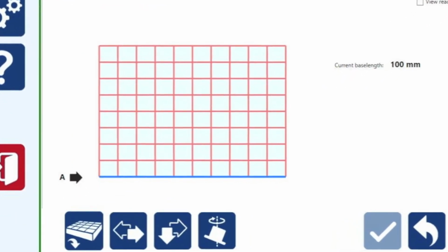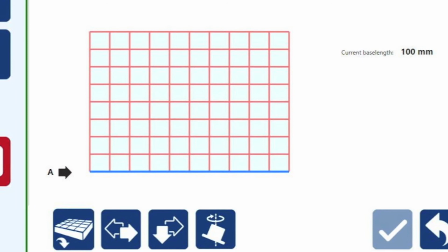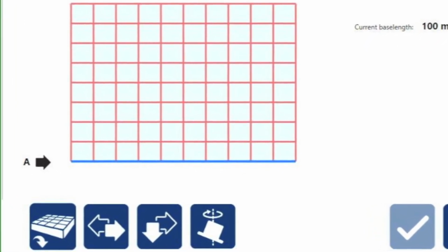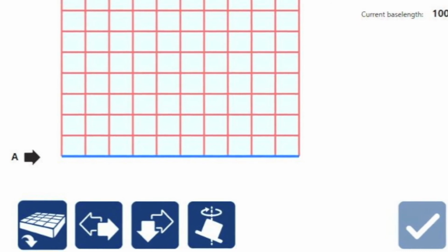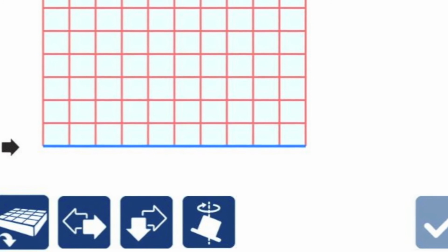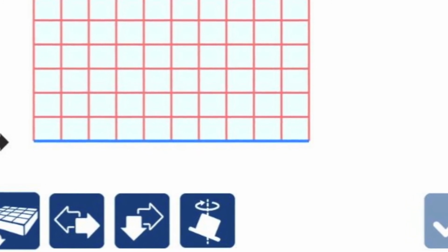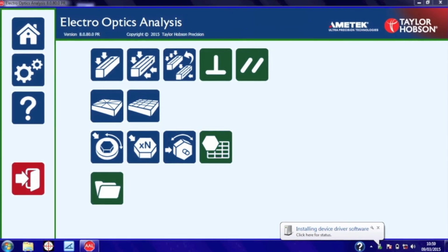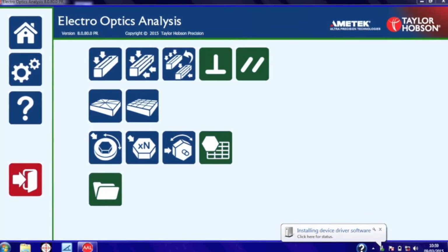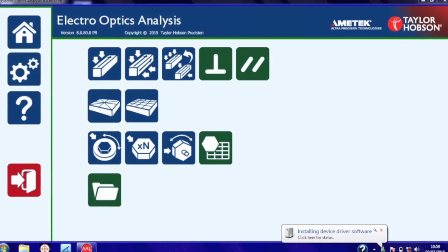This is important because we have to reference the measurement to gravity. Hence, we must reverse the Talyvel, measure it in one direction, turn it around 180 degrees, and measure it in the other direction. Then an error correction is applied to the software. Now, because the grid pattern must be referenced to gravity, you unfortunately cannot use an autocollimator to measure flatness with this pattern.